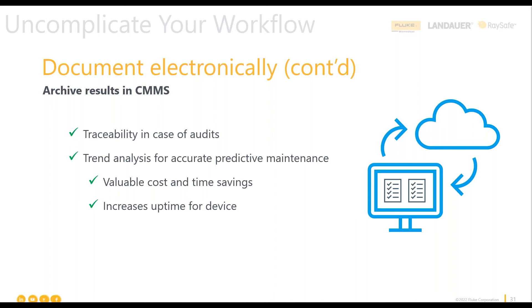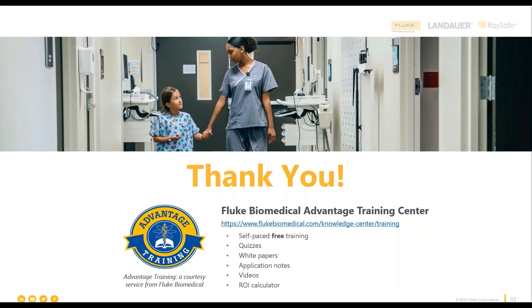Embracing automation helps a lot: it simplifies and strengthens version control, includes those manufacturer notifications, gives one source of truth for all documentation, and results are statistically sound because everybody tests the same way in the same flow and sequence. Reports are generated with little or no additional effort and files are archived automatically. This drives compliance and traceability for audits — not just Joint Commission but also FDA, which can audit your hospital and requires traceability of records. Trend analysis moves you from preventive to predictive maintenance, helping reduce costs by finding problems early while they're low-cost to fix. Visually guided workflows level the playing field from your most skilled to least skilled staff so everybody does the work the same way using the same test tools.